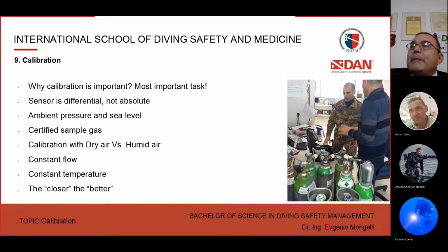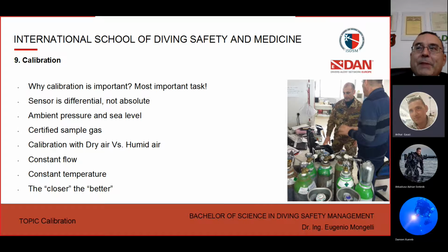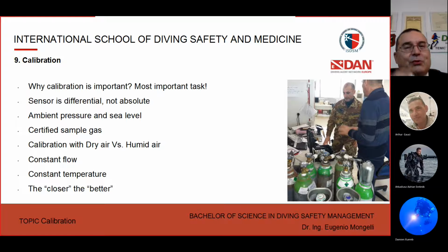What you said, the chamber, only happens if you calibrated it at 1 atmosphere. Yeah. Right? Correct. You calibrate at 1 atmosphere, you go down to 2 atmospheres, and it will read 42%. Correct. Now, if you calibrate it at 2 atmospheres, then it will come back to 21%, right? Correct. Yes, correct. This is exactly what I meant.